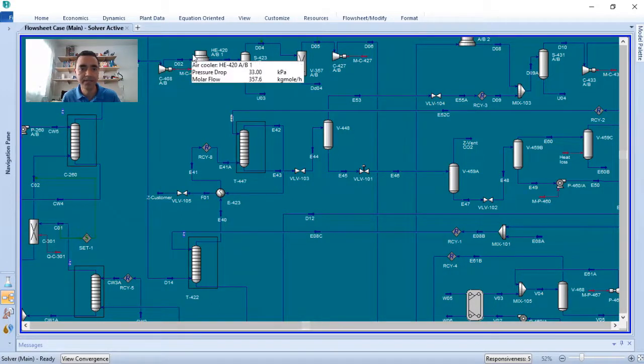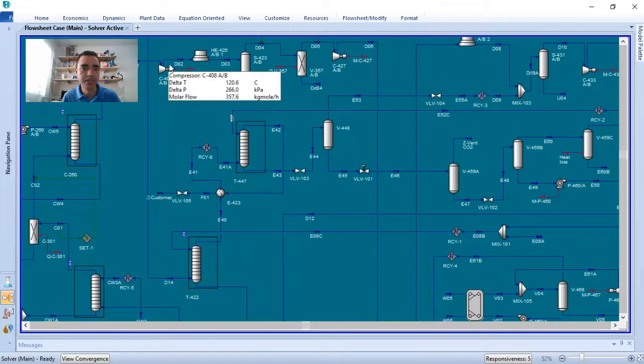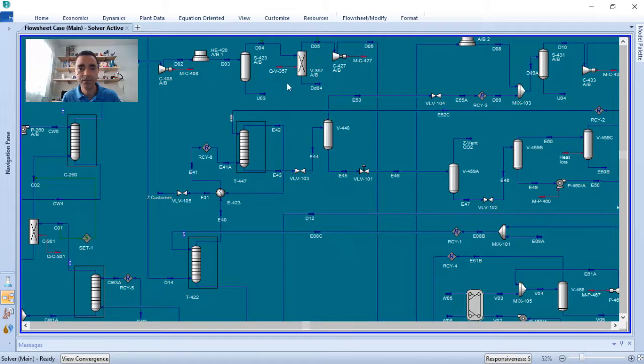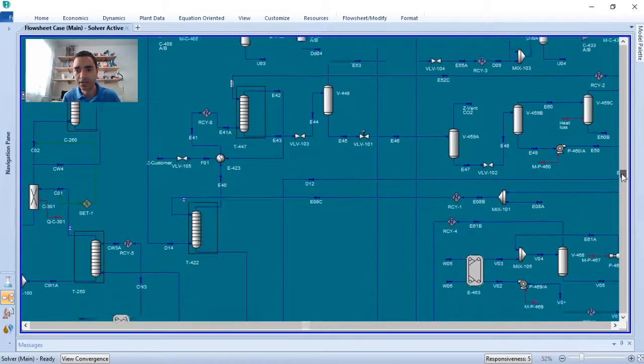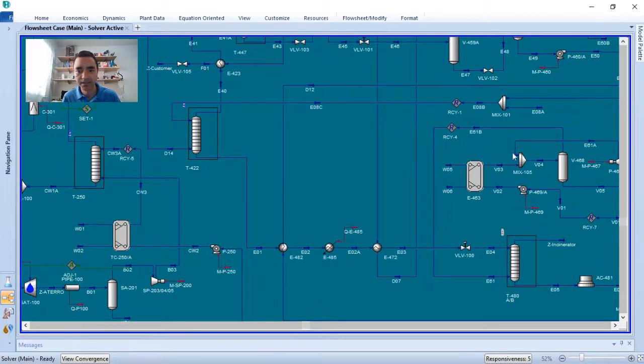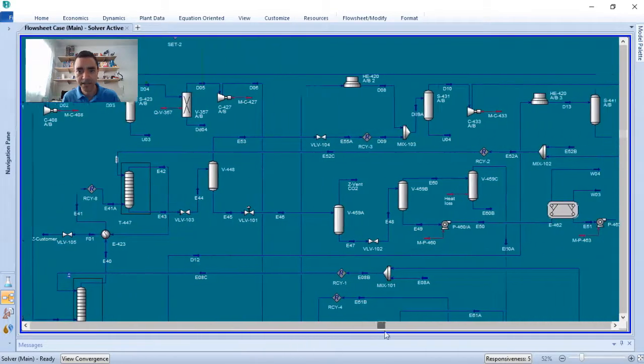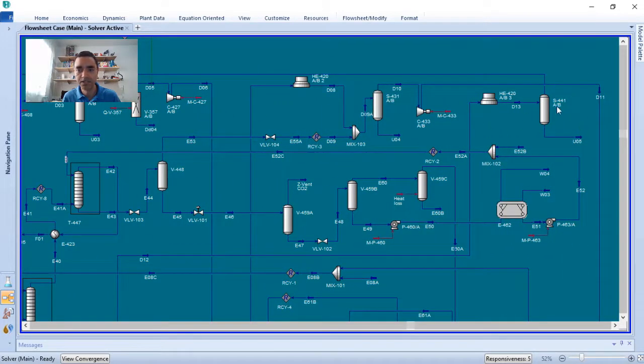compression, and because of that I have intercoolers and vessel separators, because when I increase pressure and decrease temperature, I can condense water present in this stream. I have a polishing step here where I can remove the remaining content of H2S from the gas, and I have an integration with the CO2 removal unit, and with that I increase the pressure of my biogas.